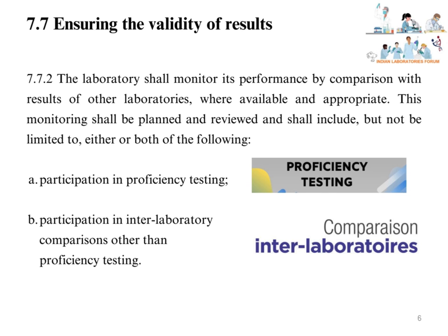Participation in proficiency testing, to prove the competency of the laboratory. Participation in proficiency testing from ISO 17043 accredited proficiency testing providers for the scope of laboratory testing. Participation in interlaboratory comparisons, other than proficiency testing. Where the laboratory is not able to find the proficiency testing for specific tests or calibration, the laboratory can initiate or participate in the interlaboratory comparisons.